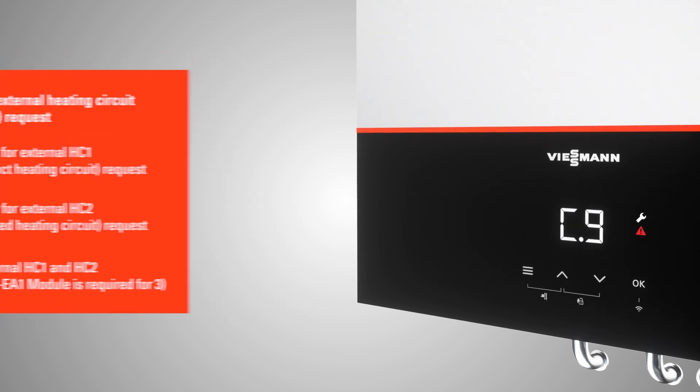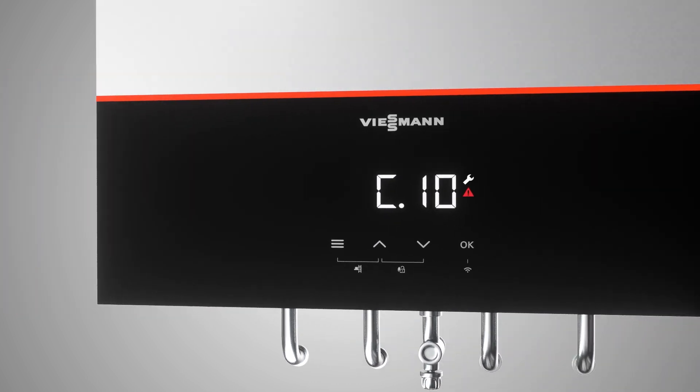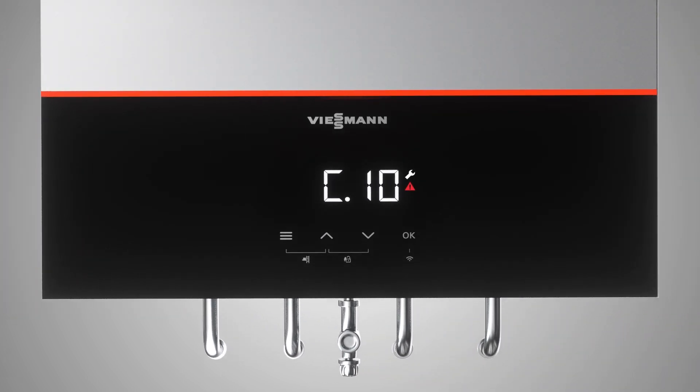More hydraulic schemes can be configured in the ViGuide app. If you selected weather compensated operation in step C7, then step C9 allows you to select which heating circuit is externally controlled. If an external EM-EA1 module is connected, select the desired option. If not, please select 0.